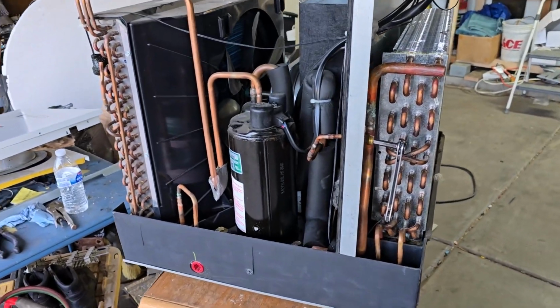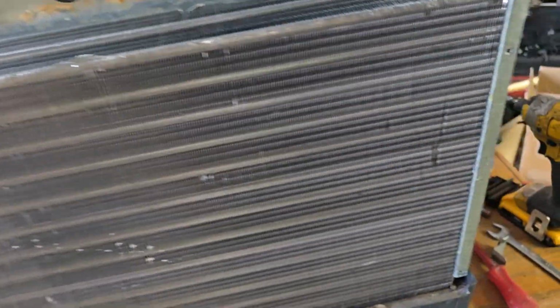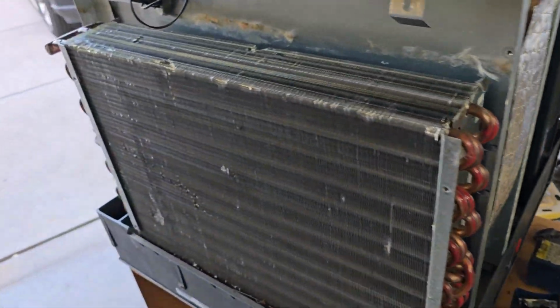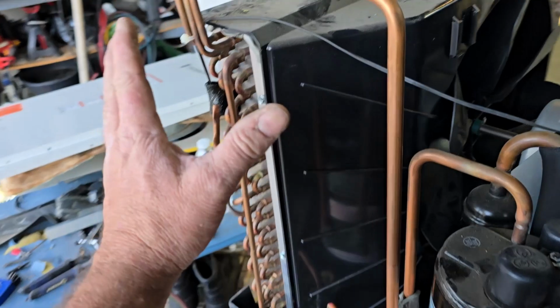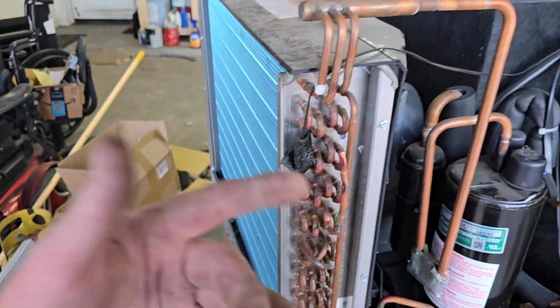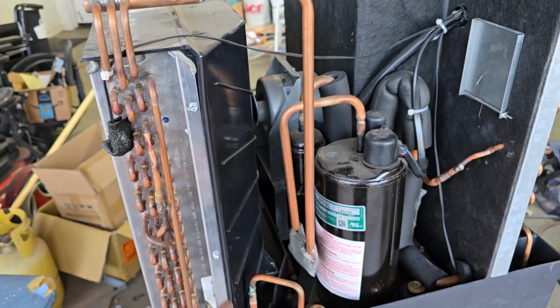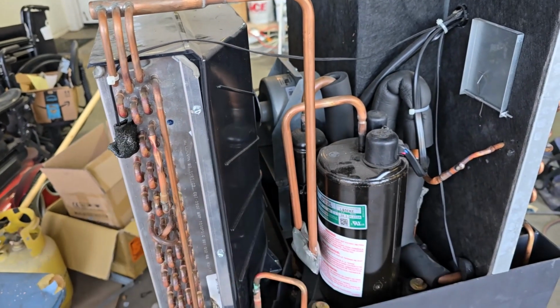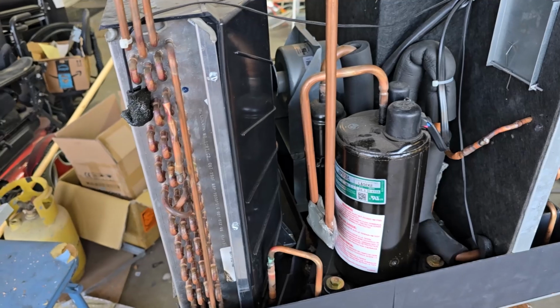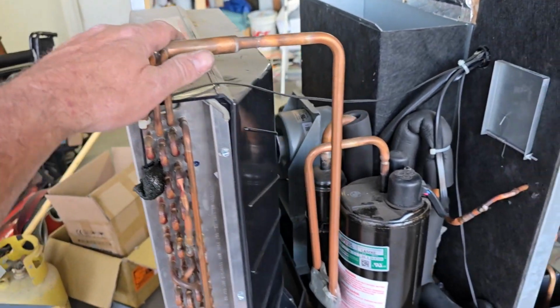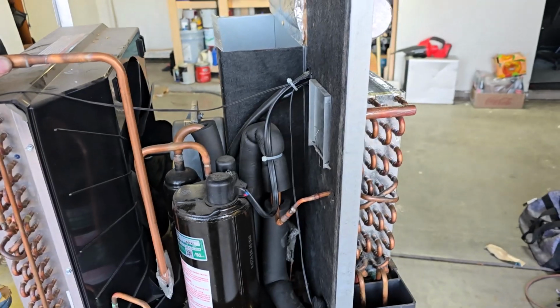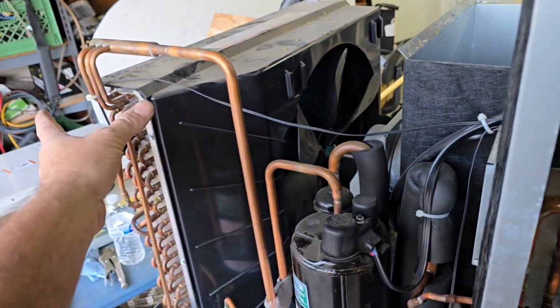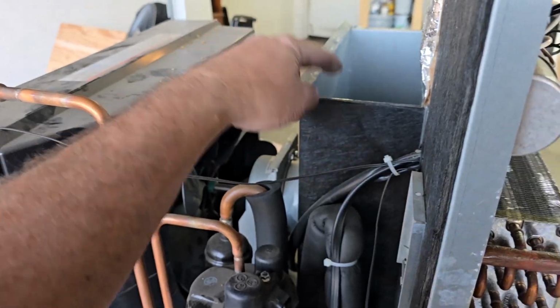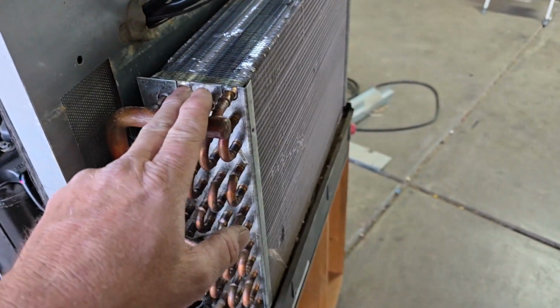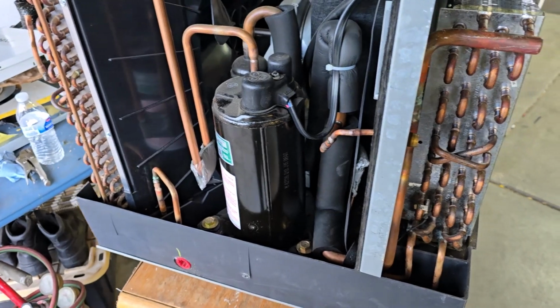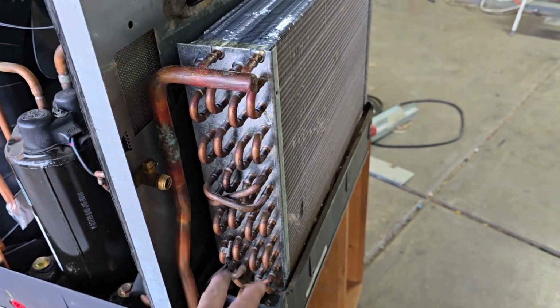Okay, got the refrigerant all recovered. Now I'm at a dilemma. My initial plan was to keep this coil for the evaporator. At first I was thinking this was a heat pump and that the coils were both going to be configured for evaporator and condenser, as a heat pump would be. However, this turned out to be a straight cool. As I've been tearing this down, it just seems like it'd be much cleaner if I use the outdoor coil with the fan and get rid of the squirrel cage section, get rid of this coil. But the dilemma here is this coil is already set up as an evaporator.